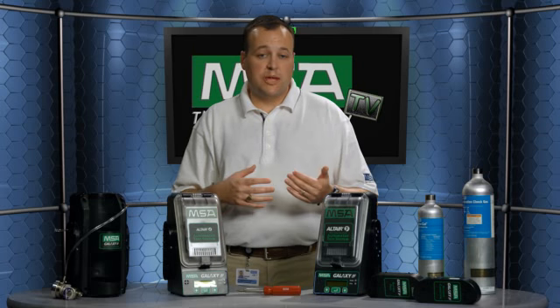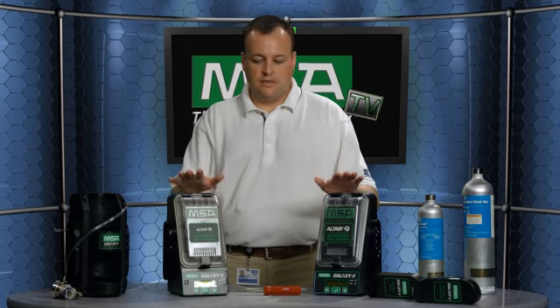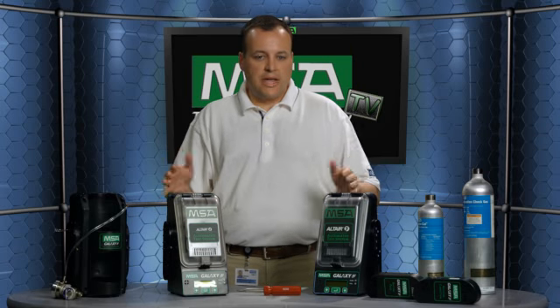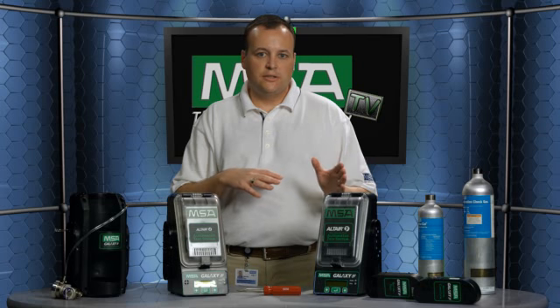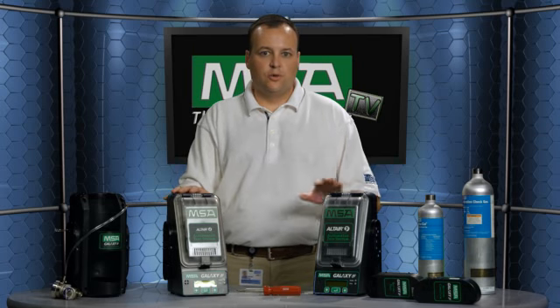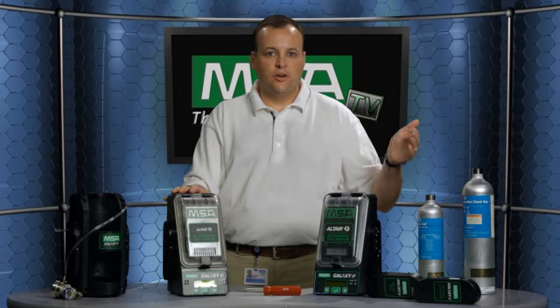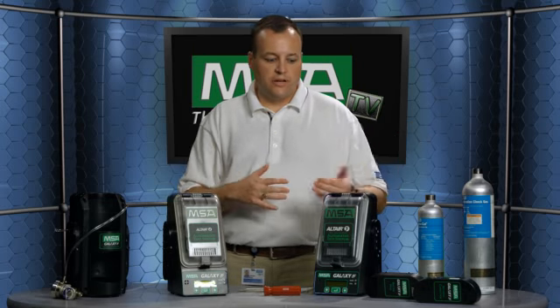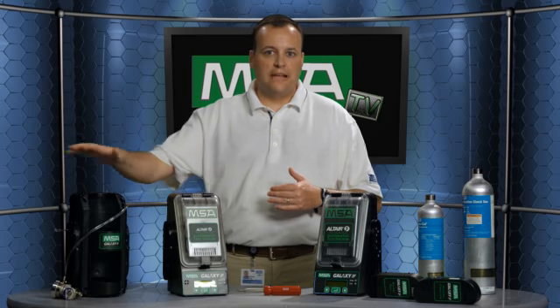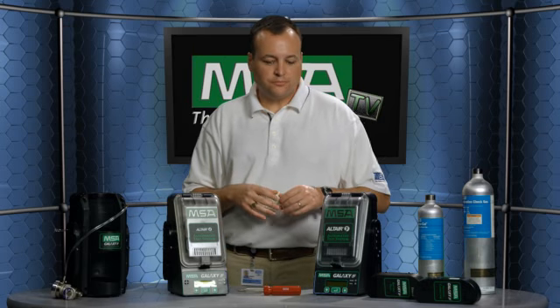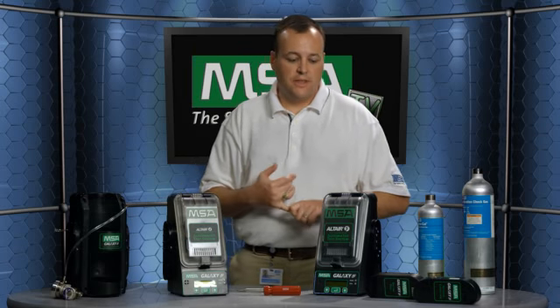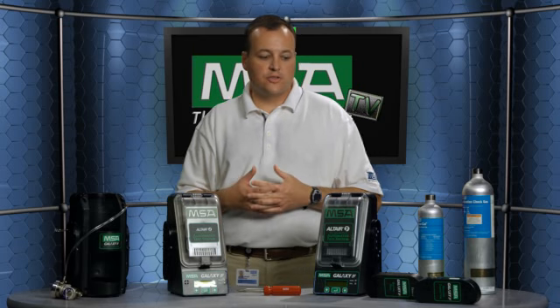It is a very much of an expandable system as well, in that you can, again, put up to 10 test stands in one bank. And what's really nice is that you get flexibility with that too, and that you can put together an Altair 4, an Altair 5, and maybe 8 Altair or Altair Pro single gas Galaxies. Really, whatever combination of Galaxies you can think of, you can use, as long as the 3 gas cylinders that you'd have would supply the correct gases that those gas detectors would need. So again, it's easy to use. It's a very flexible system. It's an expandable system. With this Galaxy system, we have a lot of great accessories as well.